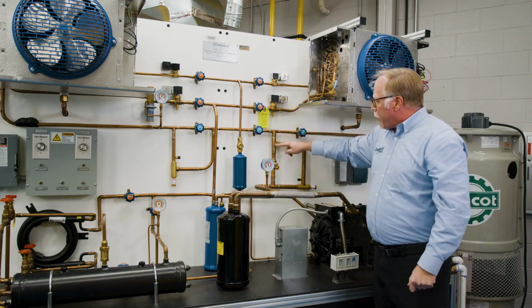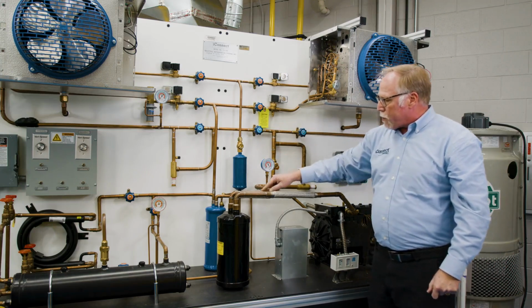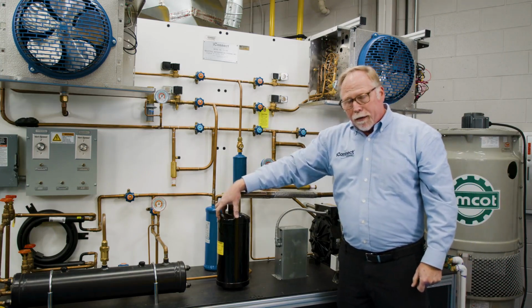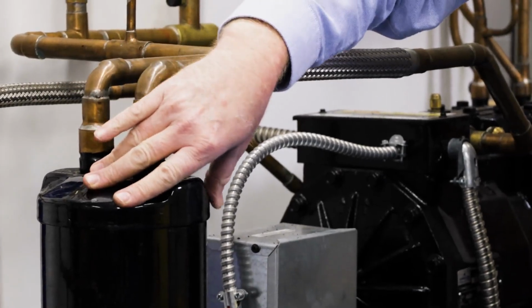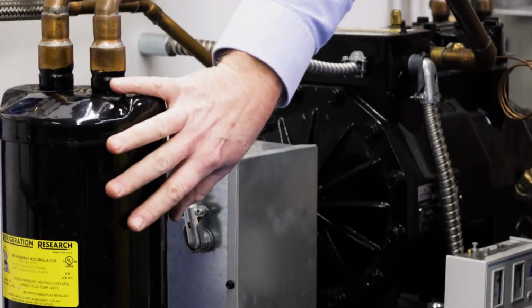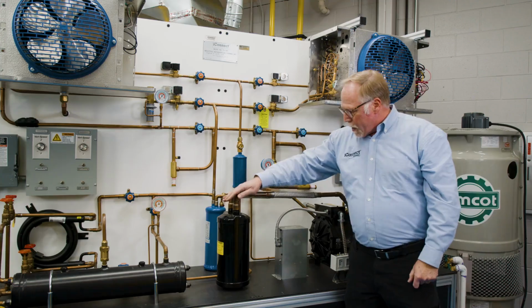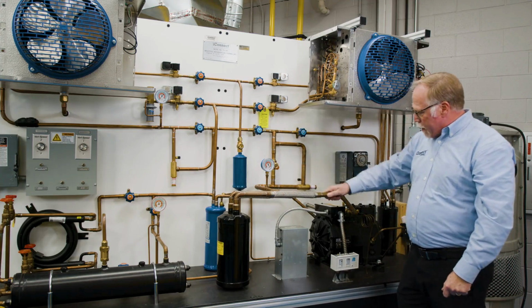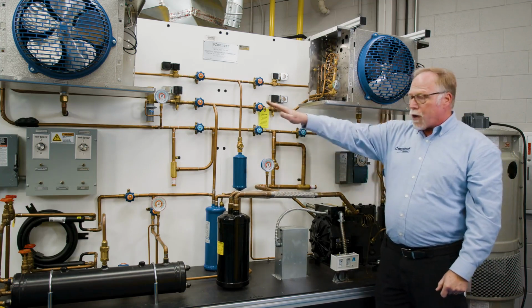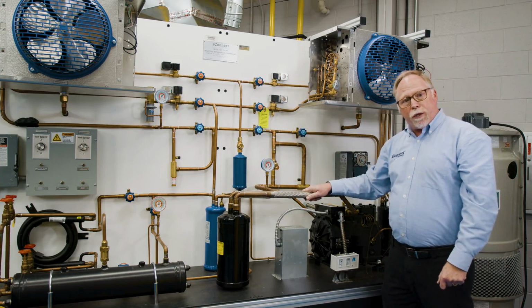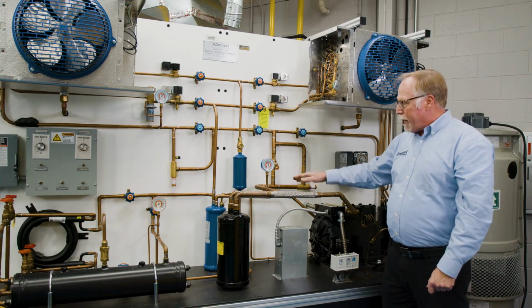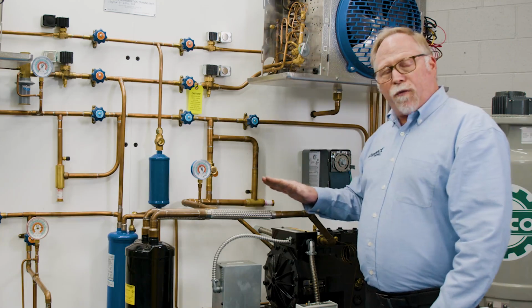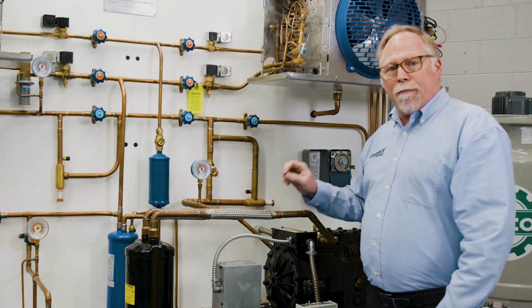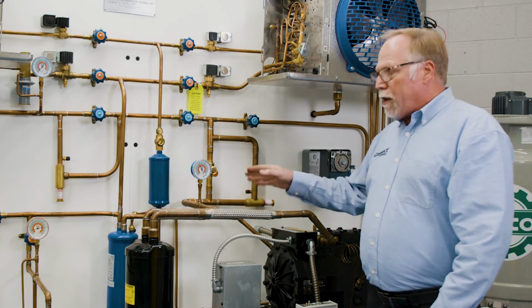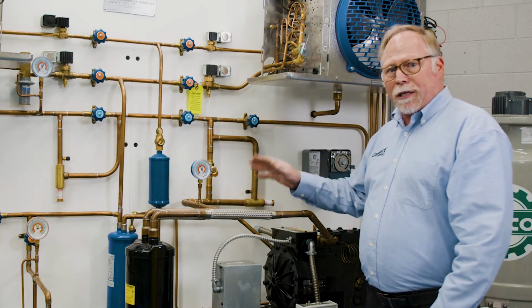Both evaporators will join here, come back through this common suction to the compressor, go through this accumulator. We have diagrams of this accumulator, and you can explain how the accumulator works, what its function is, what its importance is for the system. And then we'll come back through the vibration line, come back to the compressor, and the cycle continues all the way through. So you can use this to teach the refrigeration cycle and the condition of the refrigerant as it goes through the cycle. This is one of the first lessons that I would use this to teach, is the basic refrigeration cycle, the condition of the refrigerant as it moves through the system, and explaining how the heat is absorbed and the heat is rejected.